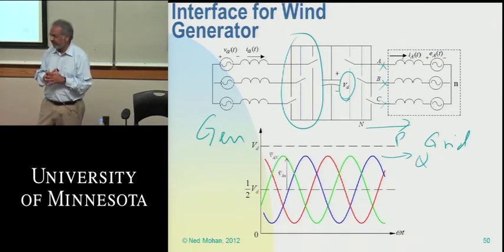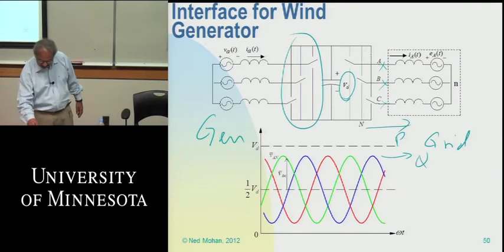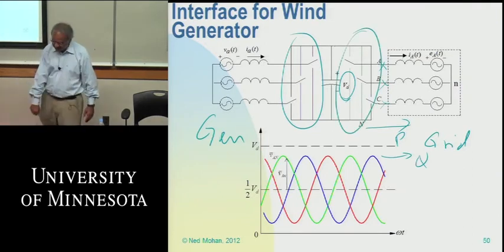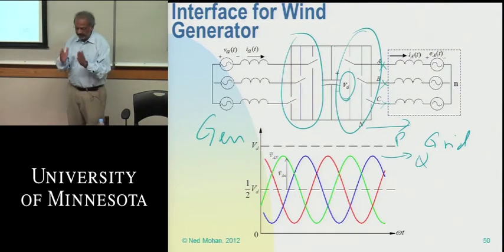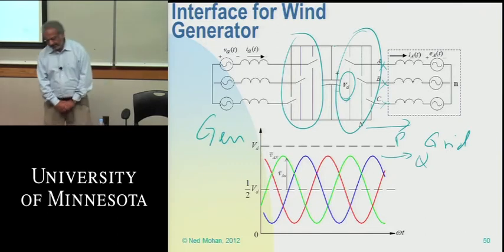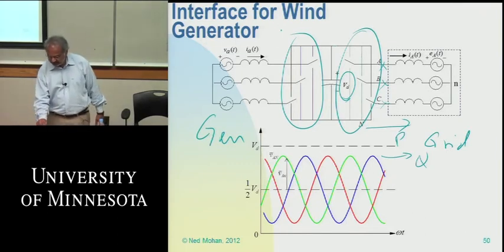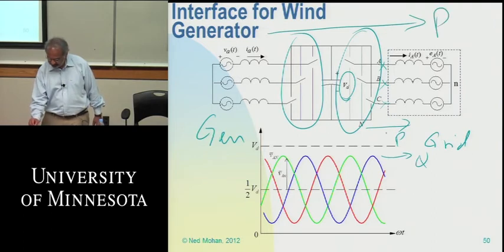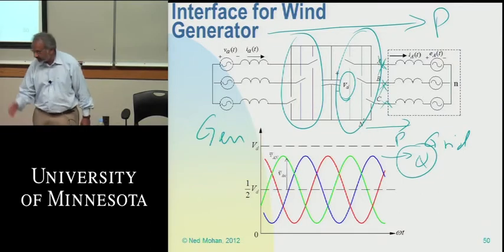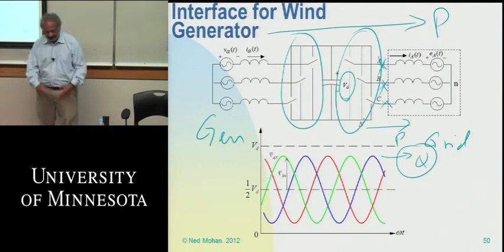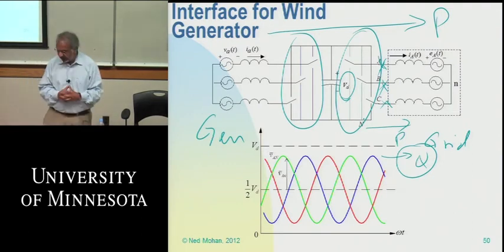You have a switch mode converter on one side connected to the generator, and another switch mode converter consisting of these three poles on the grid side, and in between, across this capacitor, you have the DC bus voltage. In this case the power flow is always in this direction, but you can also control the reactive power here by controlling the phase angles of these three voltages. That's a very significant advantage for controlling the voltage in your wind farm.